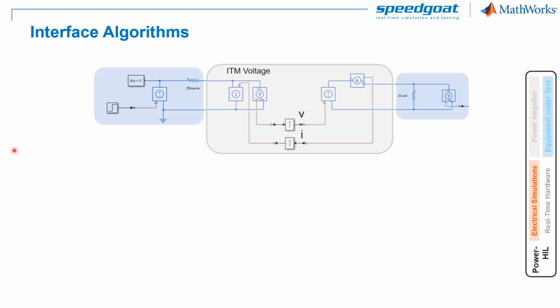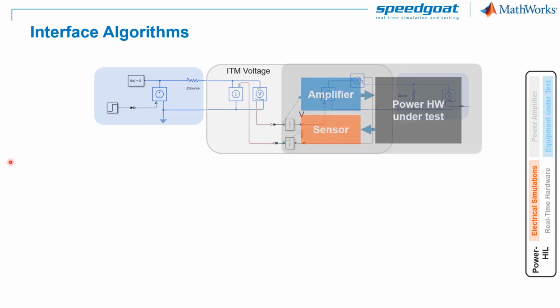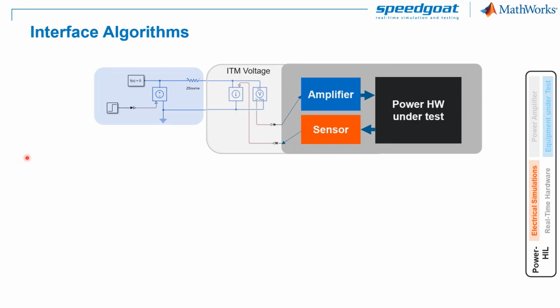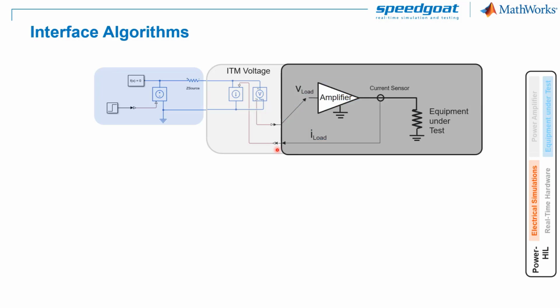Now, if we want to use a power amplifier instead of splitting the electrical network, a similar concept is used. Once again, we use an interface where we convert circuit-based electrical states into signals. But now the forward signal drives the power amplifier, and the backward signal is a measurement of the real current, in the power hardware setup, coming from a current sensor. Here in the power hardware-in-the-loop, the unit under test is driven by power output from the amplifier.